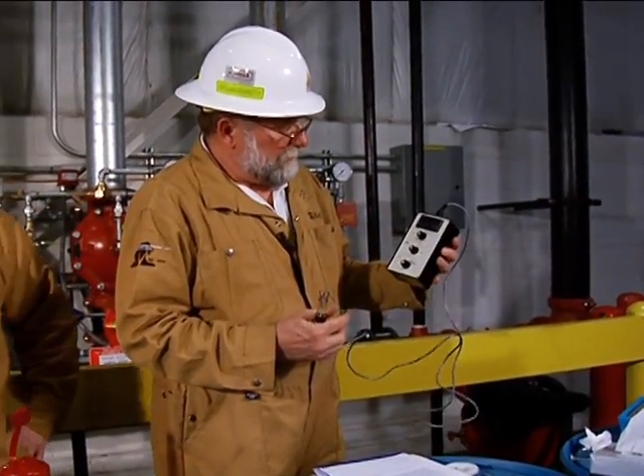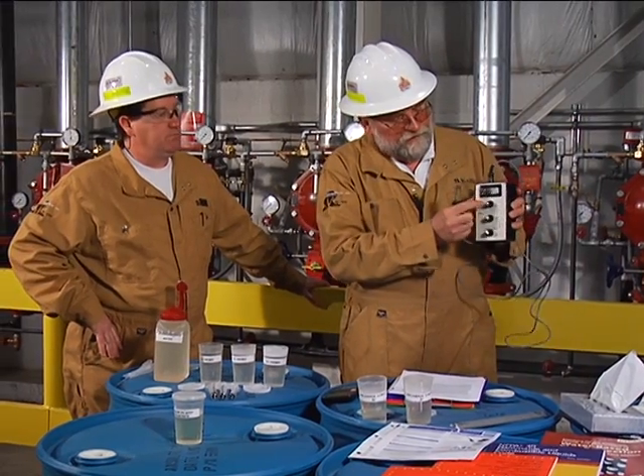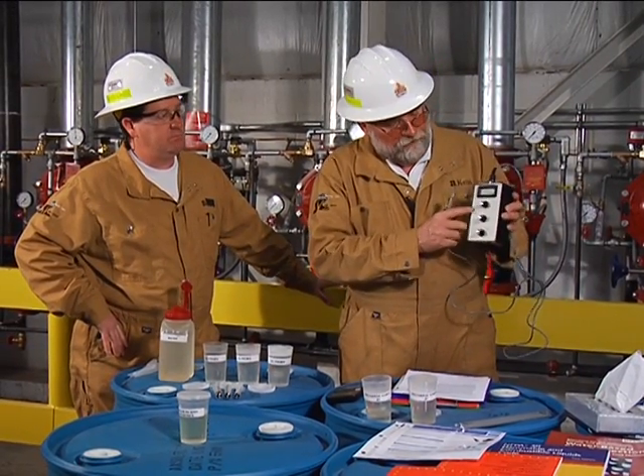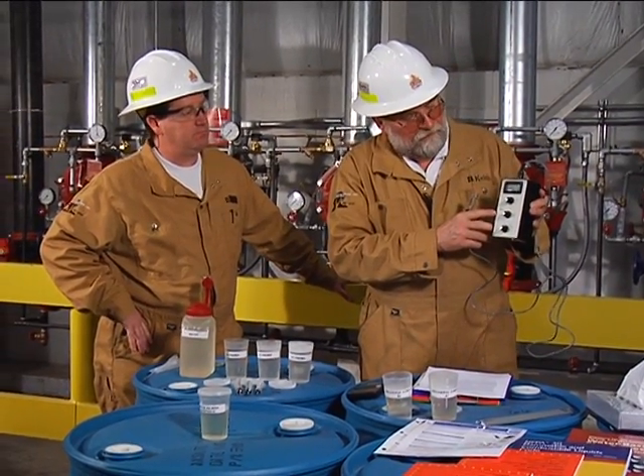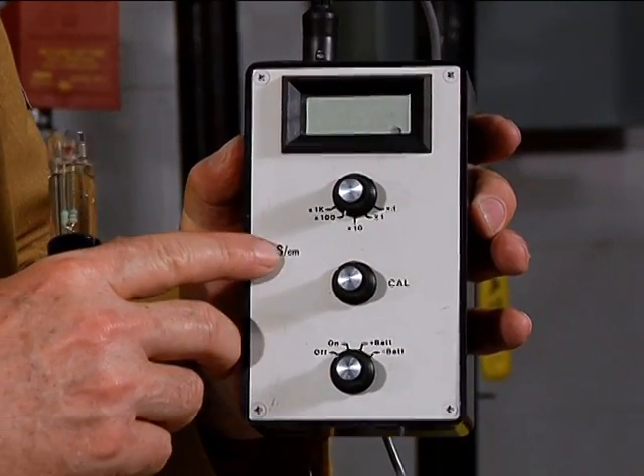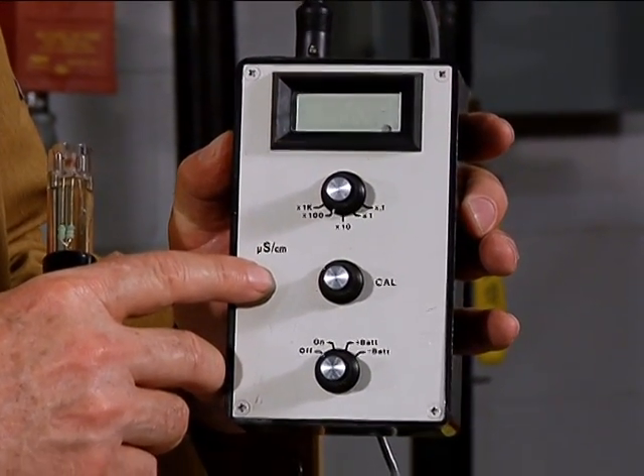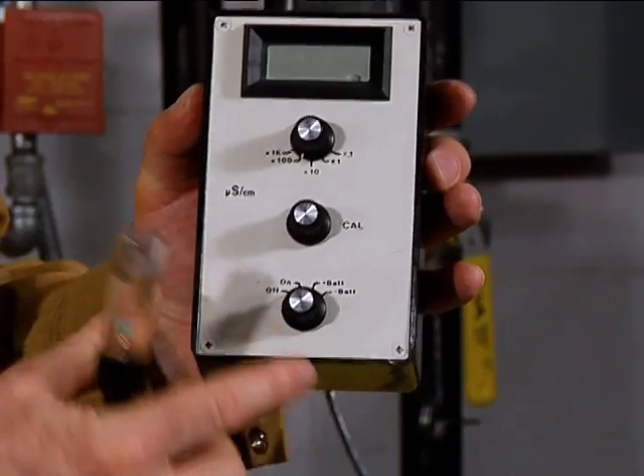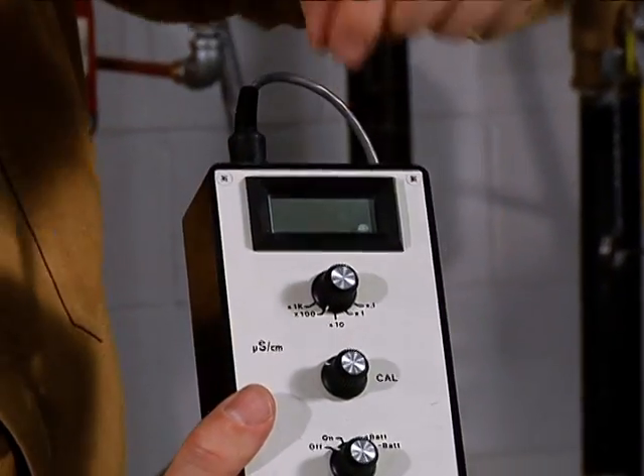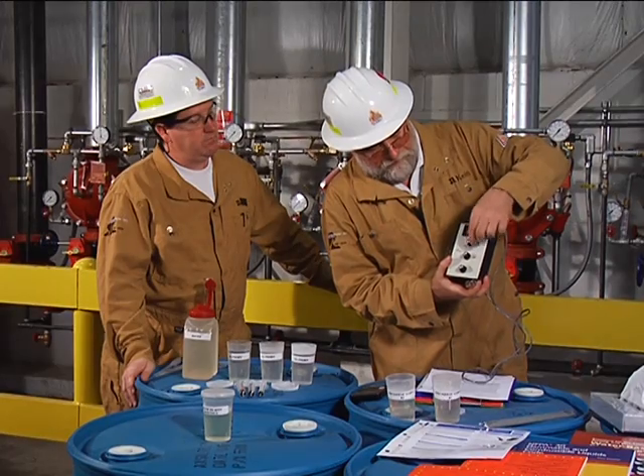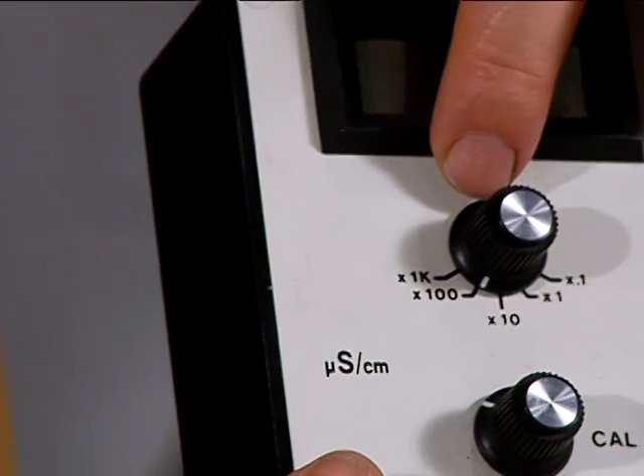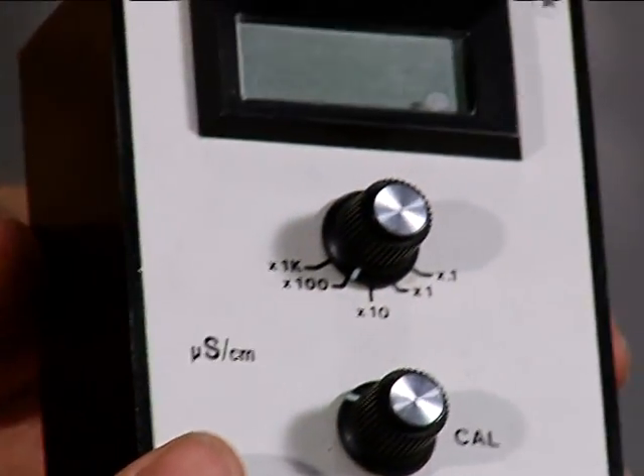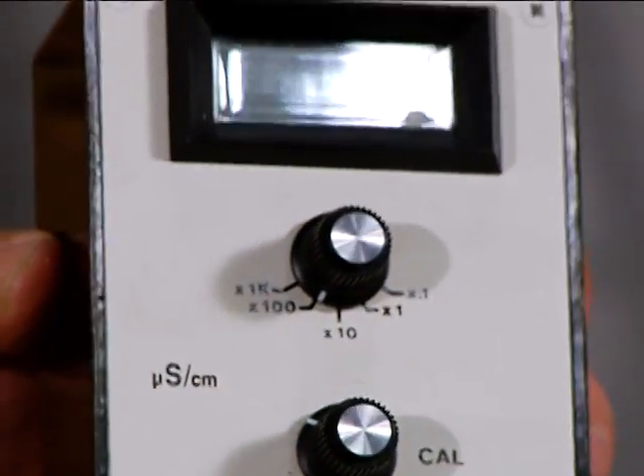Using the conductivity meter, we first need to adjust the sensitivity. We're going to be reading conductance in microsiemens per centimeter. Setting the sensitivity, we'll set it to the times 100 position that it's set now. And we'll turn the instrument to the on position.